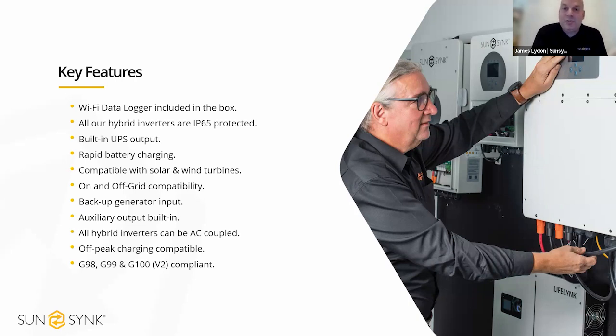Ours works a little bit different to eddies and iBoosts, where they will start diverting at 250 watts or 300 watts. The way we program our system is we tell the inverter how much power the source wants. So if it's a 3 kilowatt immersion, we will say this source wants 3 kilowatt. And if the PV is only exporting, let's say 1.5 kilowatt, the inverter will send the 1.5 kilowatt to the immersion, but the other 1.5 kilowatt we will take from the batteries. So we're giving the immersion the full amount of power that it wants. Even though it'll take little bits of power, it's happiest when it's receiving the full amount of power.